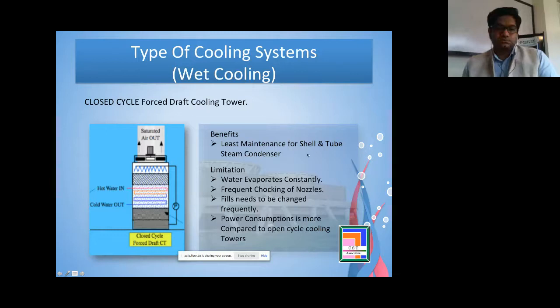Now the benefit is least maintenance for shell and tube steam condensers. See, both are going in a closed circuit, the water is not exposed, so the chances of scale formation are quite low, and the maintenance required is very, very little. All the maintenance required will be on the side of the fin tube, where the scale formation will be. But these panels can be opened and the coils can be cleaned. On the other side, the condenser on the turbine heat exchanger need not be changed. Limitations: water evaporates constantly, nozzles choke frequently, and fill needs to be changed frequently. Power consumption is more compared to the open cycle cooling tower because of the fans.